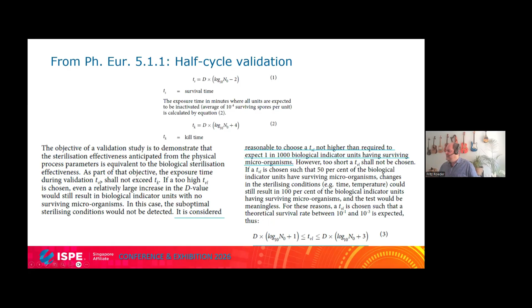So your validation time for the half cycle should be in between log 10 N plus 1 and log 10 N plus 3. Somewhere in between should be a time which results in the sterilizer in whatever, 7 minutes, or maybe a reduced temperature or something like that. But it's the time that's mentioned. So that is my idea how to bring down energy consumption in autoclaves and tunnels. To complete this topic and then move on.